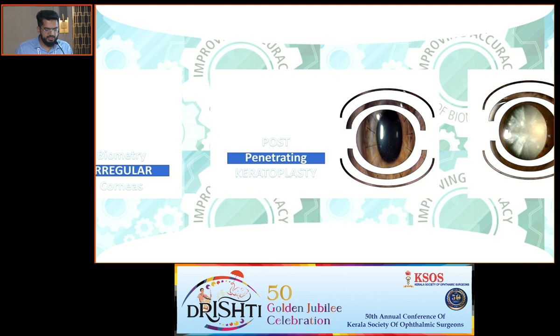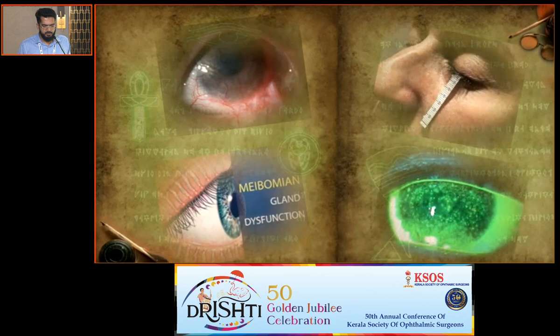So to begin with, when you're seeing a poor cornea or a bad ocular surface, we always have to keep a history of whether the patient has been using contact lenses. If the patient is on soft contact lenses, we have to ensure that they have removed them for the past 3 days. If the patient has rigid contact lenses, they should be removed for at least 3 weeks. And if it's toric, it has to be removed at least 1 week prior. And if the patient has meibomian gland dysfunction, bad dry eye or SPK, make sure this is treated first and then biometry is advised.